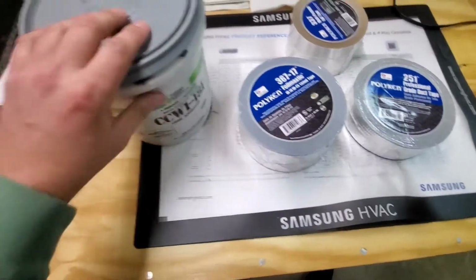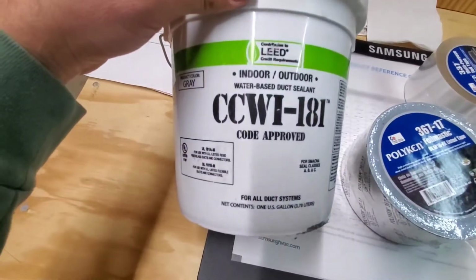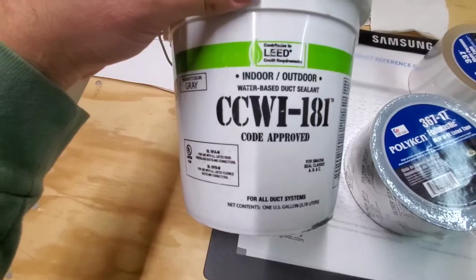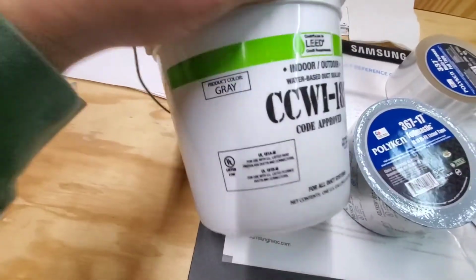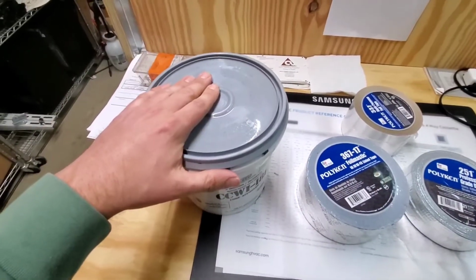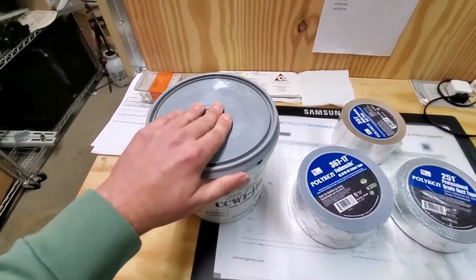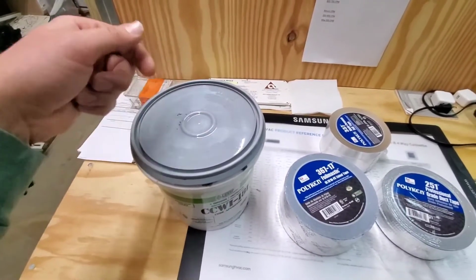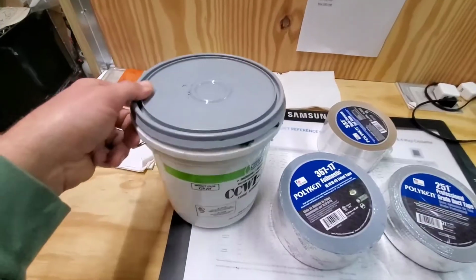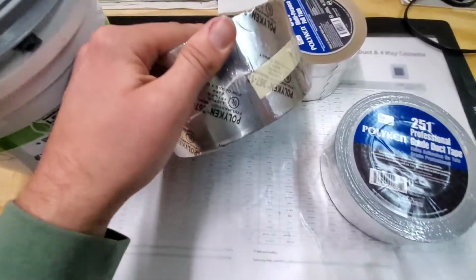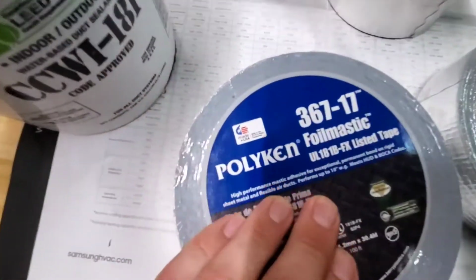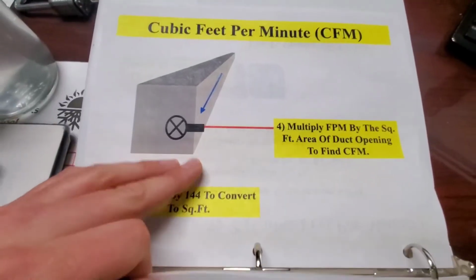Now, if you want something else that's really nice to seal the duct, this is a water-based duct sealant, okay? It's water-based, it's gray, and it's called duct butter, okay? That's a term used to describe this. You basically take a brush and you brush it on your seams, okay? Your S's and your drives. But this is great tape for sealing up your duct. Definitely check it out. I'm just going to give you some more tips here.